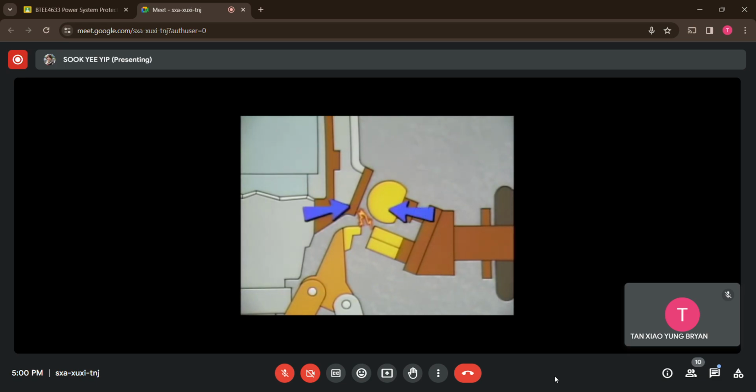An arcing probe and arcing ring are conductors that help carry the arc away from the contacts. As the contacts continue to separate, the distance between the contacts becomes greater than the distance between the arcing probe and arcing ring. The air blast through the arc path forces the arc off the contacts and across the probe and ring. The air blast continues to elongate the arc and forces it off the arcing ring into the arc chute to an arcing electrode. By this time, the air blast has stretched and cooled the arc enough so that it extinguishes at a current zero and the circuit is opened.